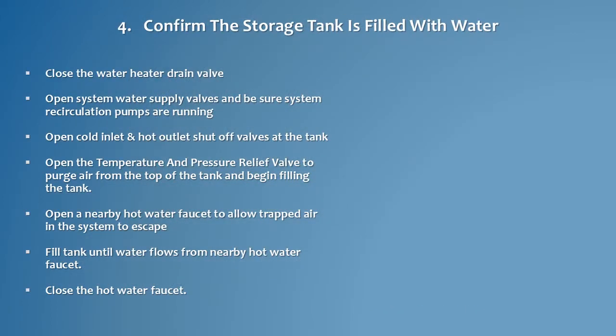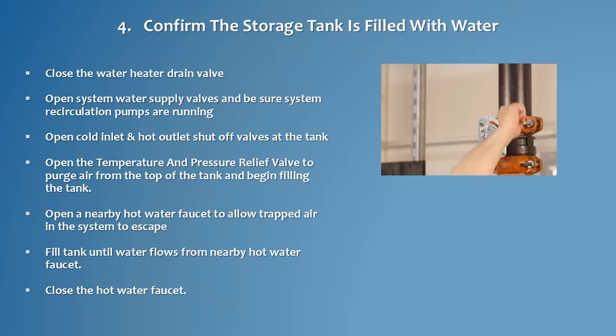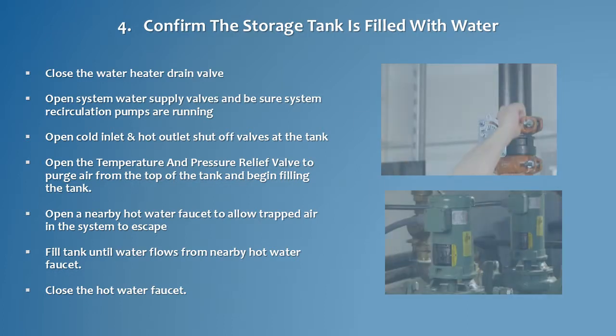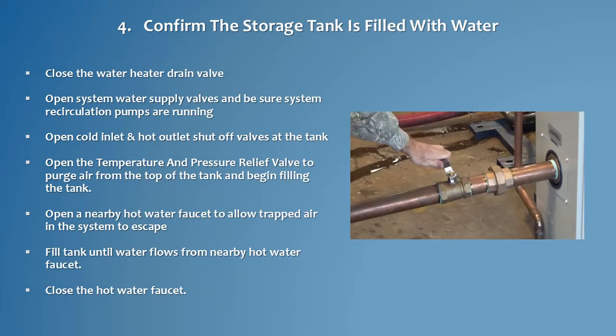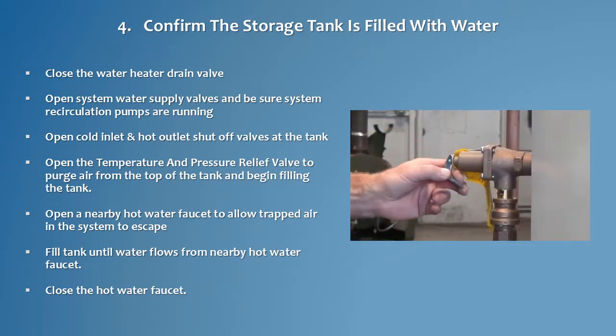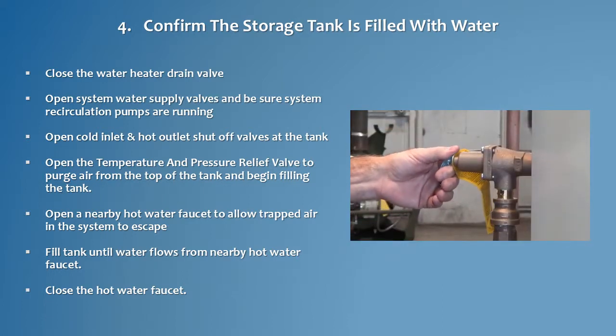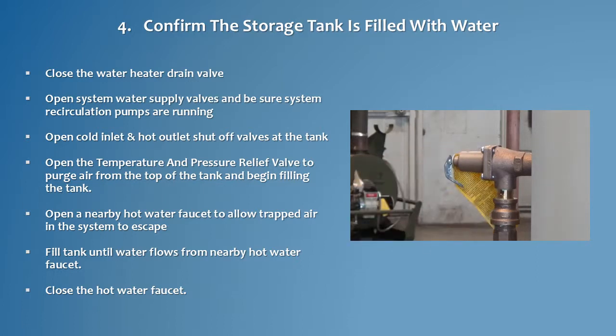With the water heater drain valve closed, open the system water supply valves and be sure that the system recirculating pumps are running. Open the cold inlet and hot outlet shutoff valves at the tank. Then open the temperature and pressure relief valve to purge air from the top of the tank and begin filling the tank. Close the relief valve when a steady flow of water is observed and continue to fill.